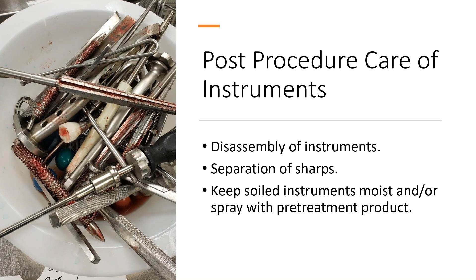Disassembly of instruments, we just talked about it a little bit, but this is very important because orthopedic cases are just growing in volume. We're talking cutting guides for tibias and femurs. We're talking spine and trauma. They all have modular screwdrivers and complex devices that need to be disassembled. Even laparoscopic instruments, at one time these were all one single piece. Now we're having modular laparoscopic instruments that come in 2 to 3, maybe even 4 pieces. And items like Da Vinci disposable accessories need to be removed at the point of use. A lot of times it's hard to tell there's an accessory on that instrument. Or maybe there's a tech in SPD that doesn't recognize that accessory for what it is and that it needs to be removed.